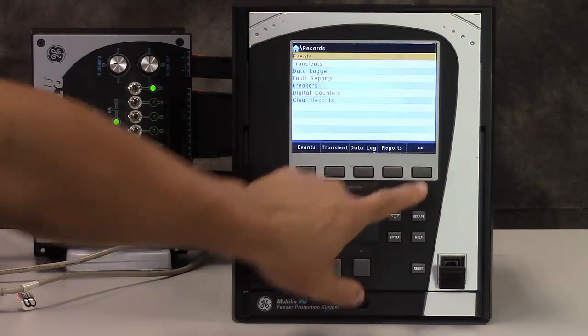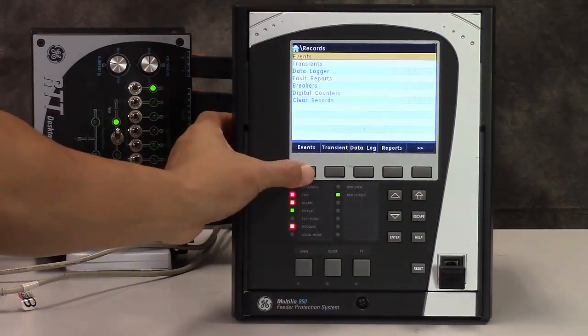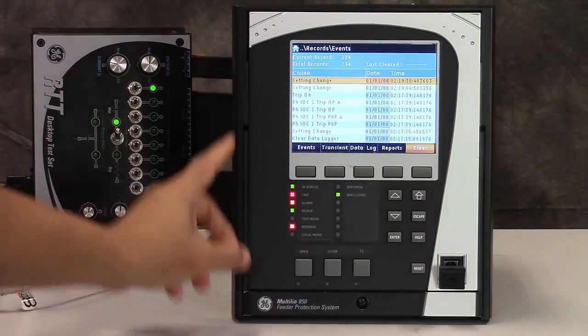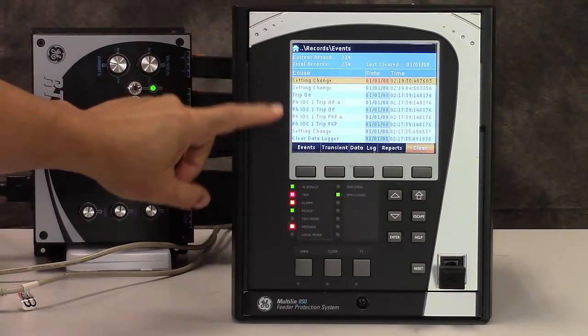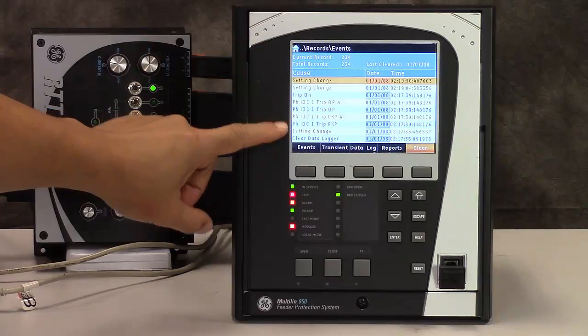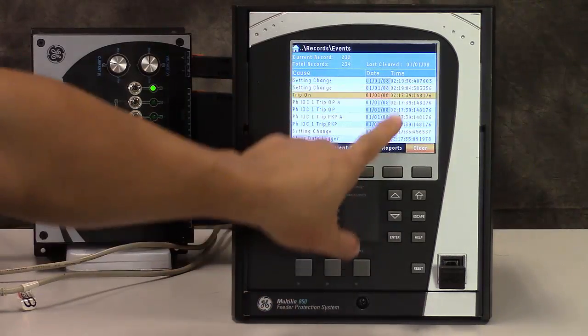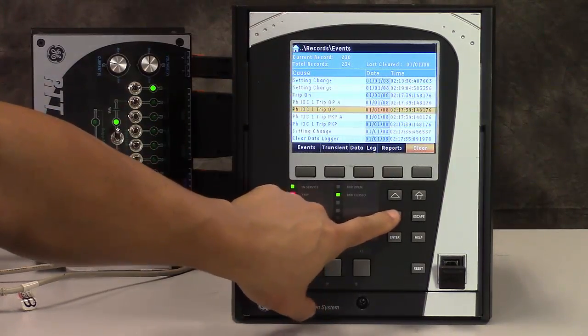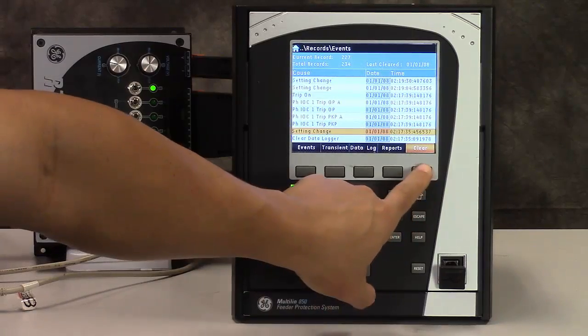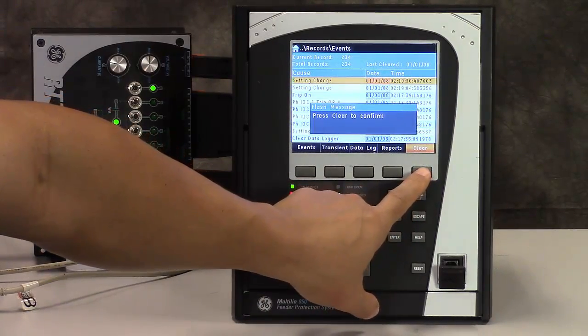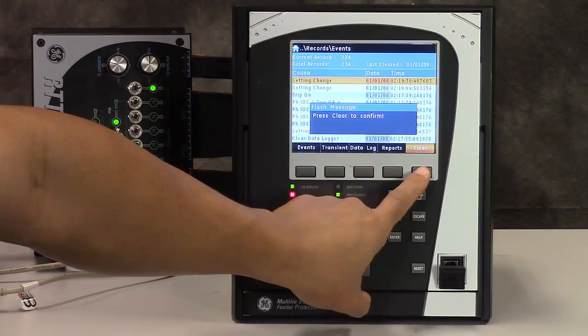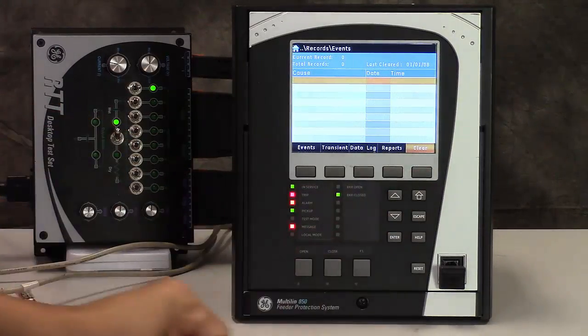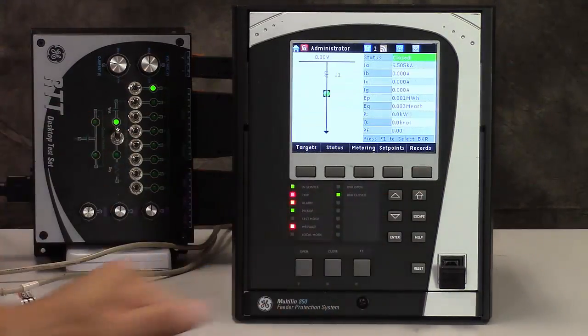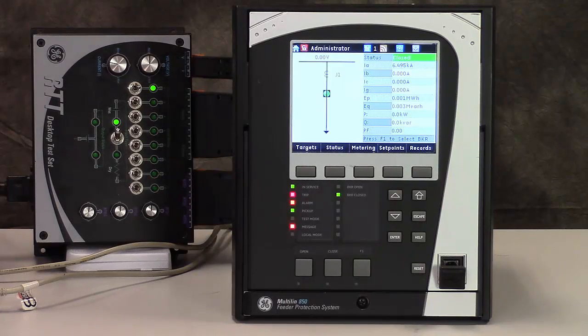And in the records, we can check the events, what element has operated. There's an event recorder. You can see the timestamps for each event. And this can also be cleared by pressing the clear button. Press clear to confirm. So that's the basic operation with the front panel.